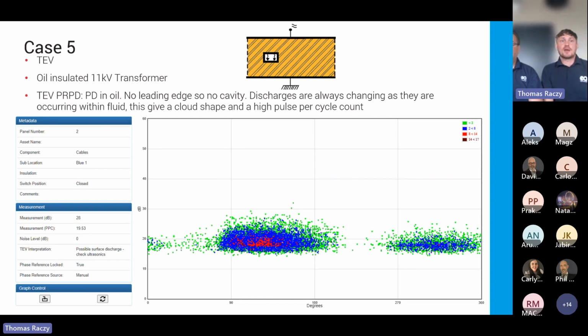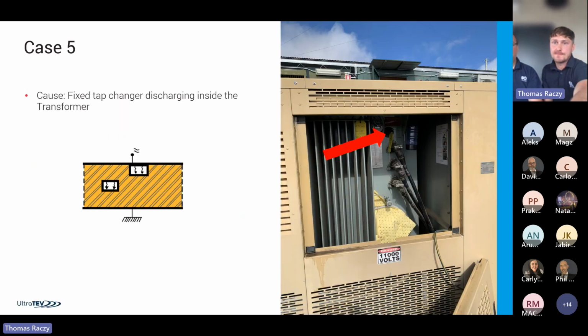Another case study is from an oil-filled 11 kV transformer. We presented you before typical patterns for PD in oil, and we mentioned it's quite intense. So there's a lot of different colors here, red colors coming into play. So quite high intensity. You can see that there's almost 20 pulses per power cycle. So the discharges in oil gear tend to be very intensive. There's a cloud shape, and that was found to be a faulty or discharging tap changer. So the issue was with the tap changer.